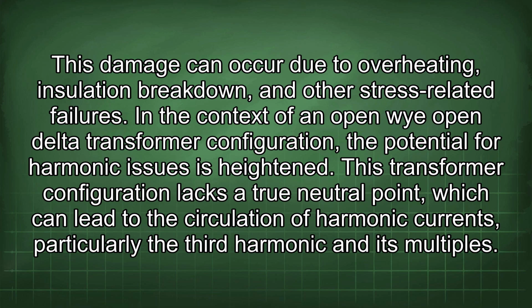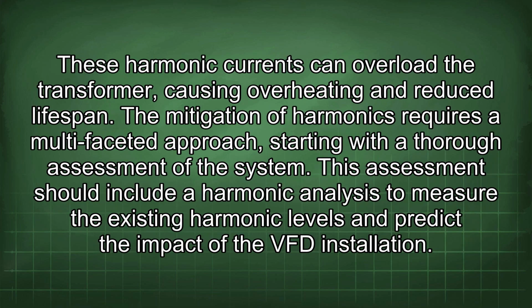In the context of an open Y-open delta transformer configuration, the potential for harmonic issues is heightened. This transformer configuration lacks a true neutral point, which can lead to the circulation of harmonic currents, particularly the third harmonic and its multiples. These harmonic currents can overload the transformer, causing overheating and reduced lifespan. The mitigation of harmonics requires a multifaceted approach, starting with a thorough assessment of the system.